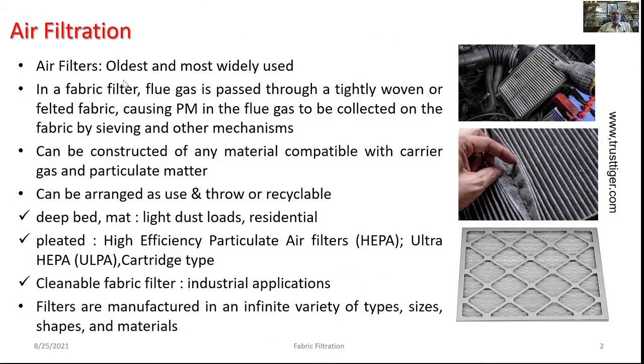Air filtration is the oldest and most widely used control method as far as particulates are concerned. In a fabric filter, the flue gas is passed through a tightly woven or felted fabric causing the particulate matter to be collected on the surface or within the body of the fabric by sieving or other mechanisms. These fabric filters can be constructed of any material compatible with the carrier gas and the particulate matter, and they can be used as throw type or recyclable type.